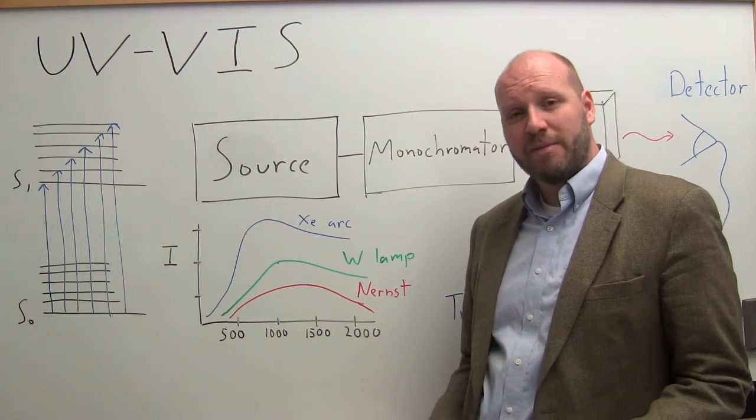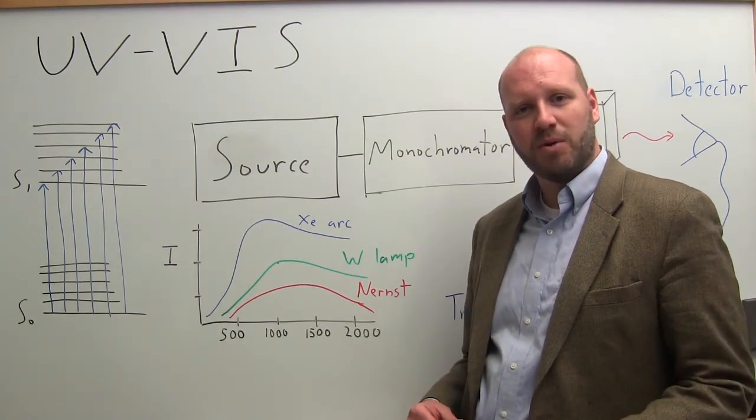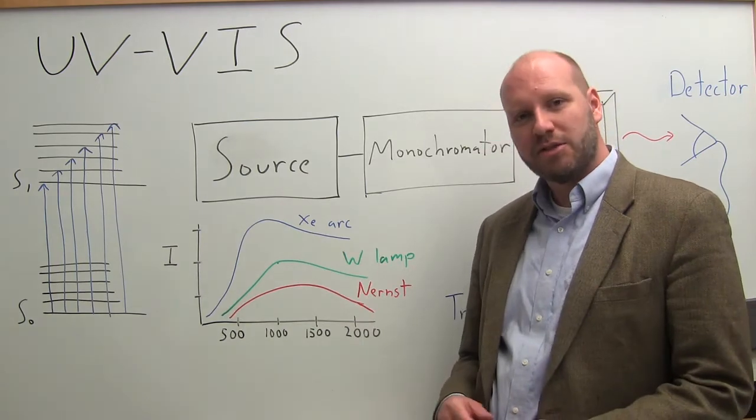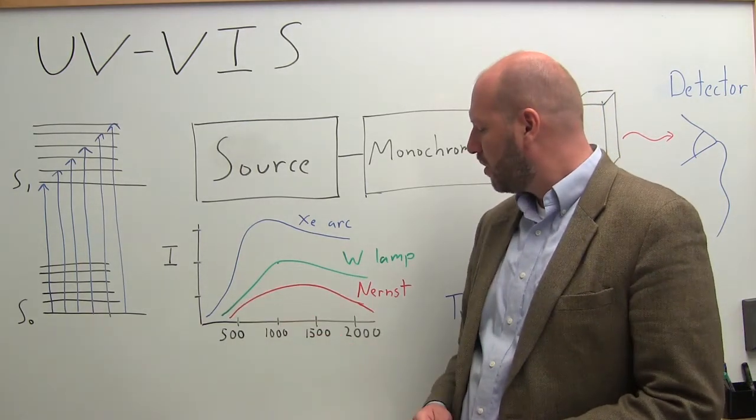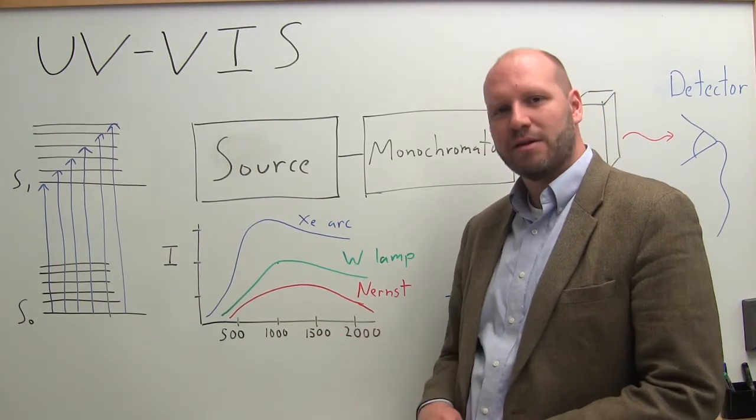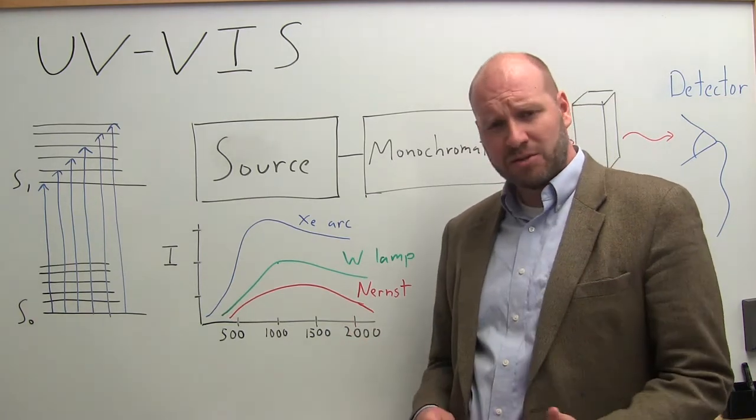Now what I start with is my lamp source, and these are typically light bulbs - things like tungsten lamps, Nernst glowers, xenon arc lamps. They each have a different intensity versus wavelength range. This is the wavelength in nanometers on this axis, and that's going to control the figure of merit for your measurements.